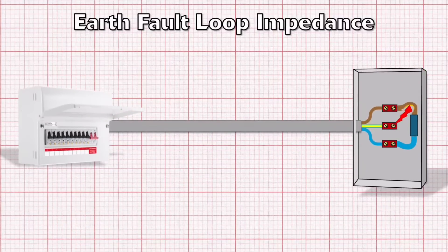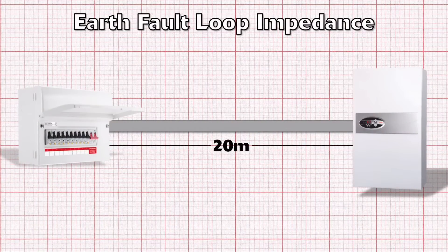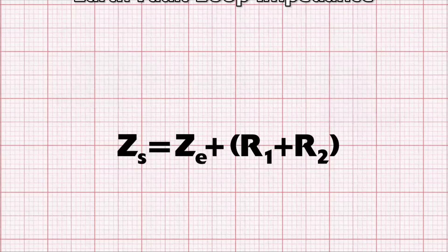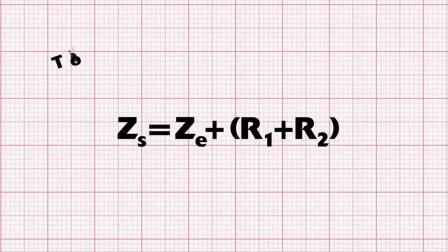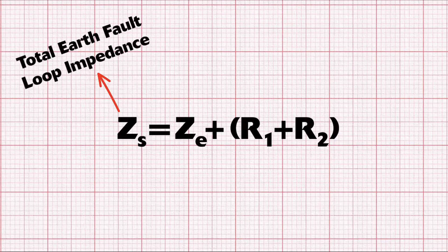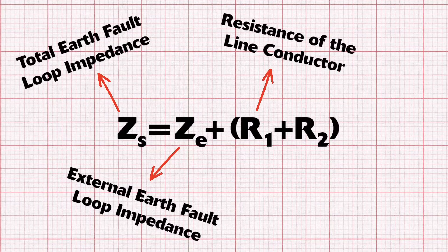In our electric boiler circuit that's simple because there's only one load. To calculate earth fault loop impedance we use the formula: ZS = ZE + (R1 + R2). ZS is the total earth fault loop impedance we're trying to find. ZE is the impedance of the earth fault loop path external to the building. R1 is the resistance of the line conductor and R2 is the resistance of the CPC. Combined, these give the total impedance of every part of the earth fault loop path.